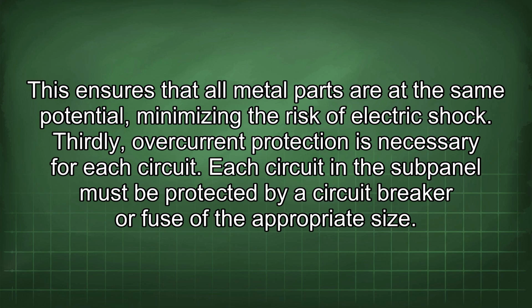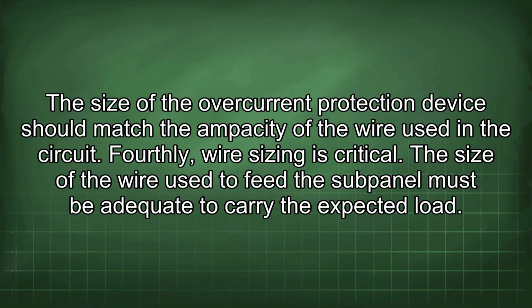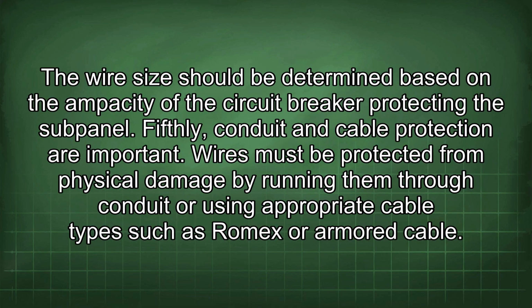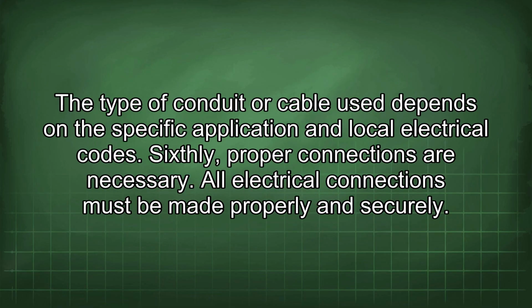Thirdly, overcurrent protection is necessary for each circuit. Each circuit in the subpanel must be protected by a circuit breaker or fuse of the appropriate size. The size of the overcurrent protection device should match the ampacity of the wire used in the circuit. Fourthly, wire sizing is critical. The size of the wire used to feed the subpanel must be adequate to carry the expected load. The wire size should be determined based on the ampacity of the circuit breaker protecting the subpanel. Fifthly, conduit and cable protection are important. Wires must be protected from physical damage by running them through conduit or using appropriate cable types such as Romex or armored cable. The type of conduit or cable used depends on the specific application and local electrical codes.